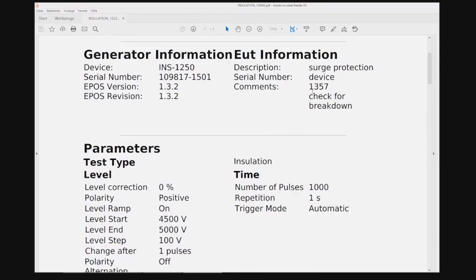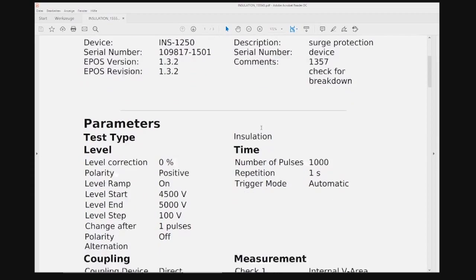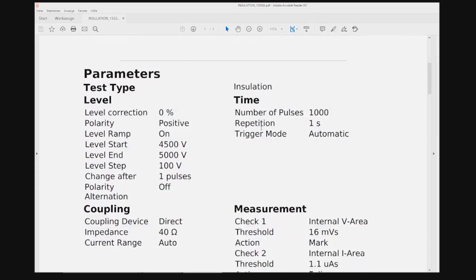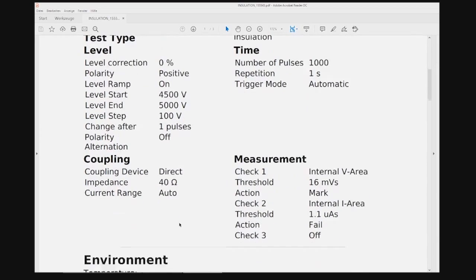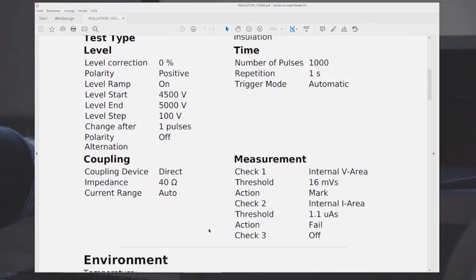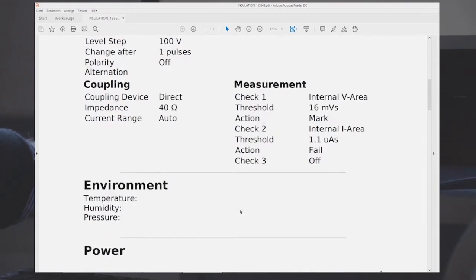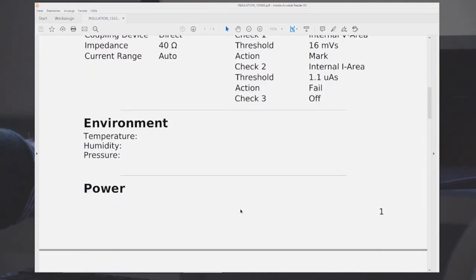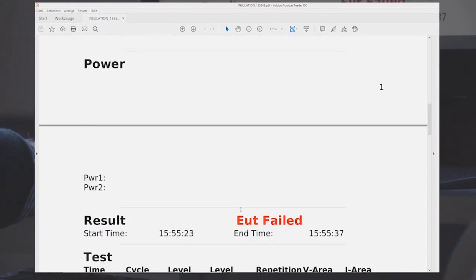So the test report copied from the generator can be viewed on the computer. We see the generated serial number, some information that's been entered by the user, then the test setup parameters: voltage, number of pulses, impedance, then the measurement circuit. Here we spoke about the check thresholds that we can set in the generator, and then we come to the actual measurement results.